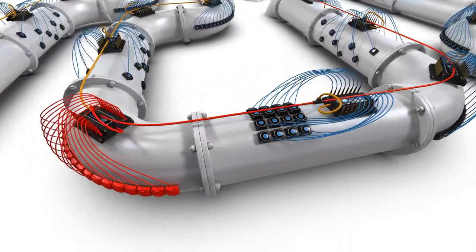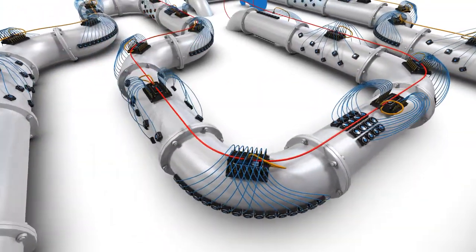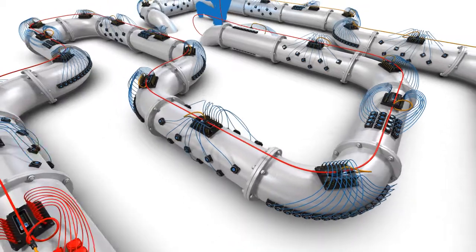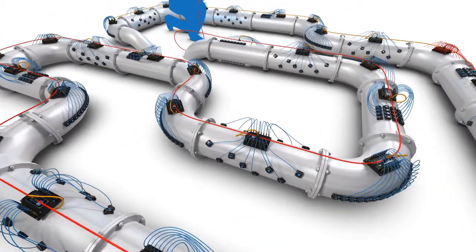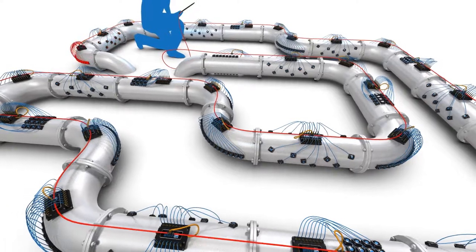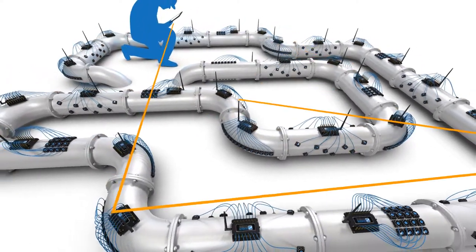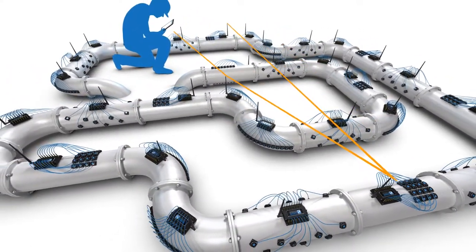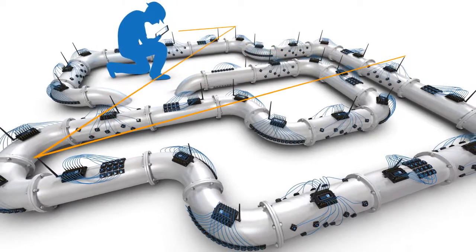In this manner, measurements are automatically gathered from a network of up to 32 DSIs, representing a maximum of 512 individual transducers, all on a single multi-drop cable stretching as far as 1,000 feet, or alternately, over a wireless mesh network.